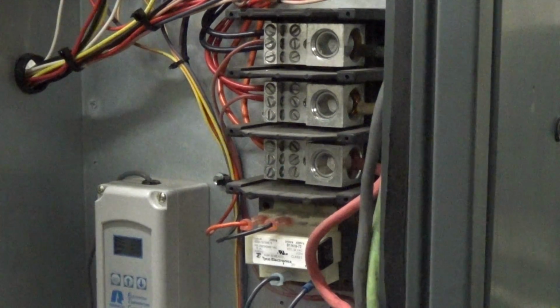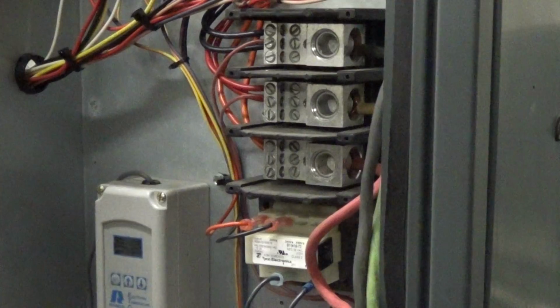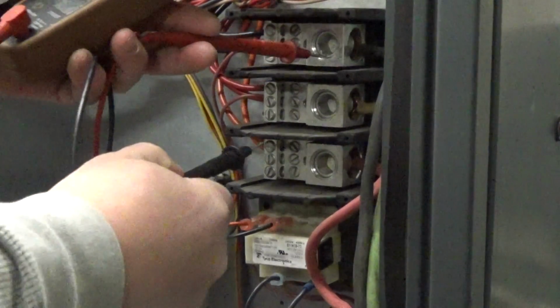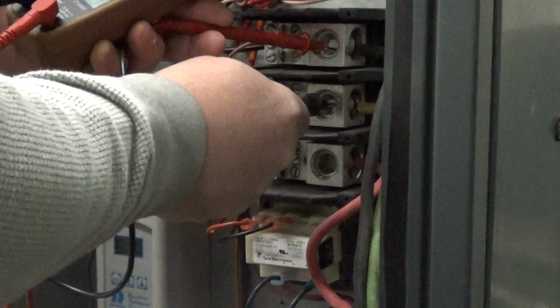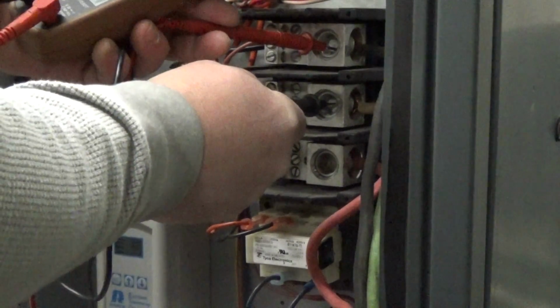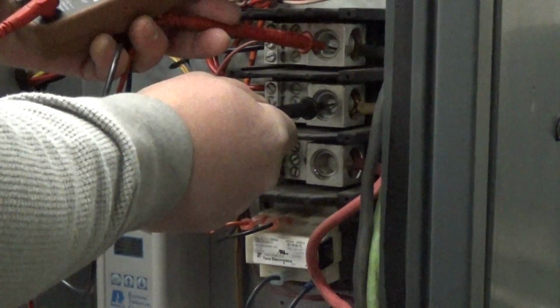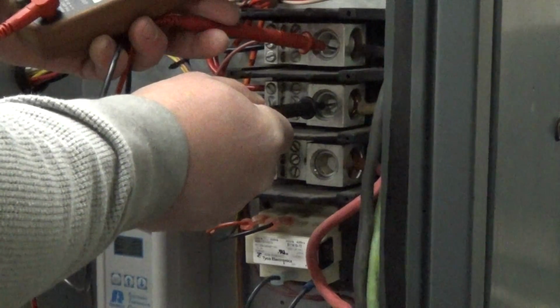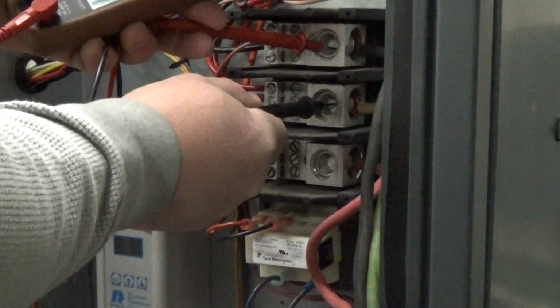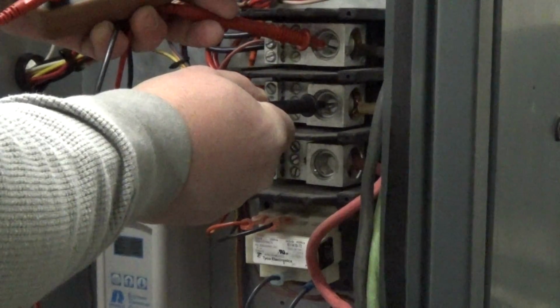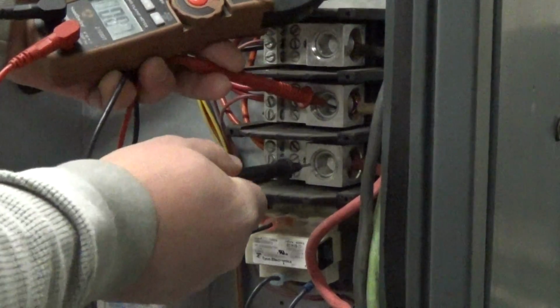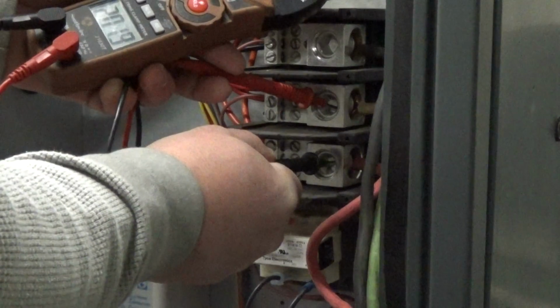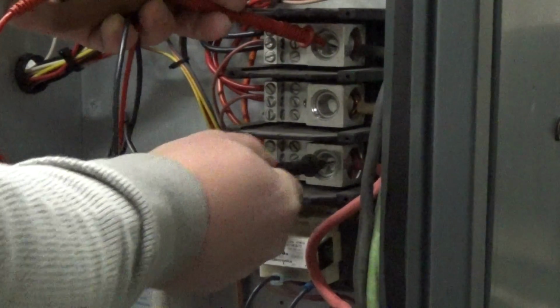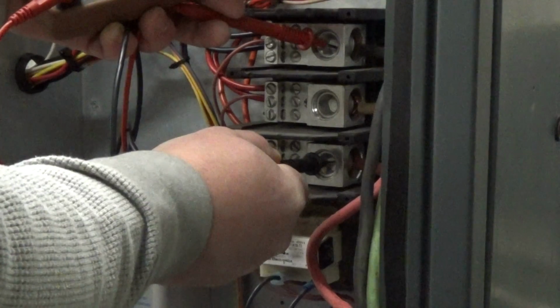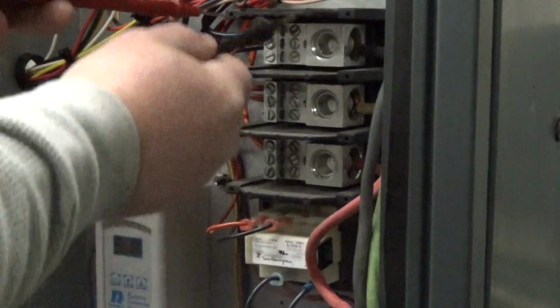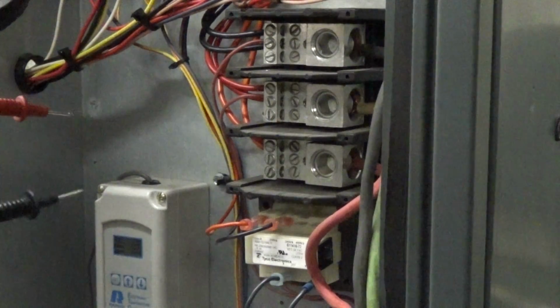So, in this type of 3-phase power, we've got it on AC. Between each hot leg, and you should have a licensed electrician do it, of course, only. Actually, we're even a little bit lower today. We're at 202 volts between the top two, 202 volts between the bottom two, 202 or 203 volts between the top and the bottom. So between any hot legs, you should be measuring your 3-phase voltage.